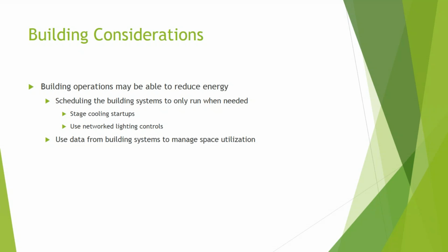In the first webinar, I showed the example of a large peak demand that occurs first thing in the morning if the chillers start up, or the rooftop units start up at 4 or 5 in the morning, long before anybody's showing up for work. By staging that and having some of the units cycle earlier in the day, but not having all of them come on at once, you can save considerable energy and also reduce peak demand charges.